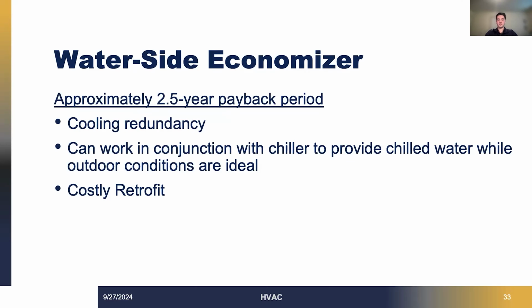Similar to an airside economizer, a waterside economizer recycles water within the chilled water loop to cool the building. This recycled water can be utilized to cool the building while bypassing the refrigeration loop in the chiller we discussed earlier. While implementing a waterside economizer can lead to significant cost savings over time, it is important to note that the retrofitting of this equipment can be expensive. The installation process typically requires substantial equipment and piping modifications, making it a considerable investment for facilities to enhance their energy efficiency.